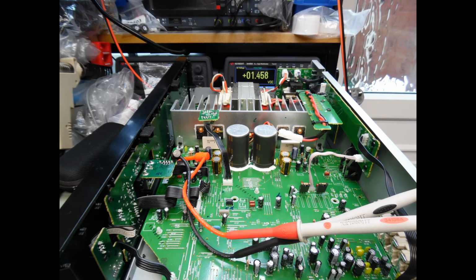When I did the measurement here it was high, as you saw. But if you measure the voltage on the base of each transistor - depending on whether it's PNP or NPN, it'll be positive or negative - it should be about 1.2 volts or minus 1.2 volts. On the defective channel, it was around 0.5, almost below the turn-on voltage for the device.